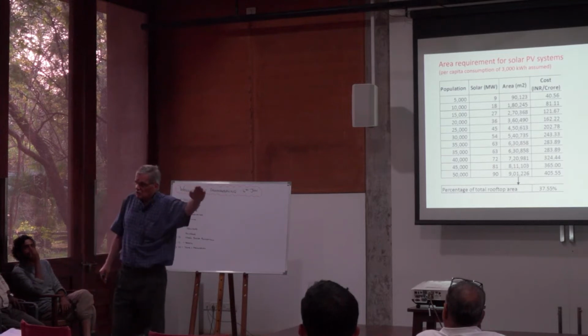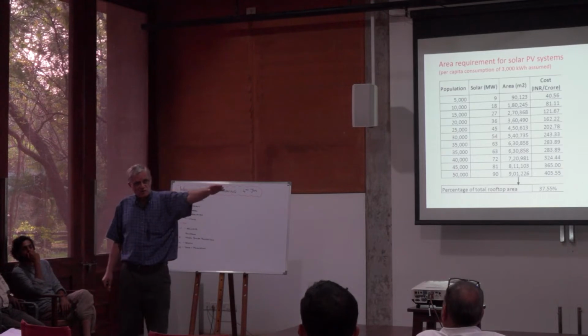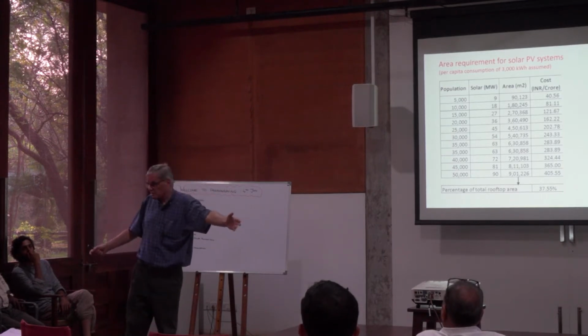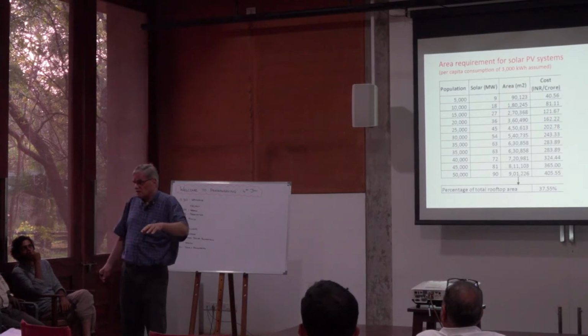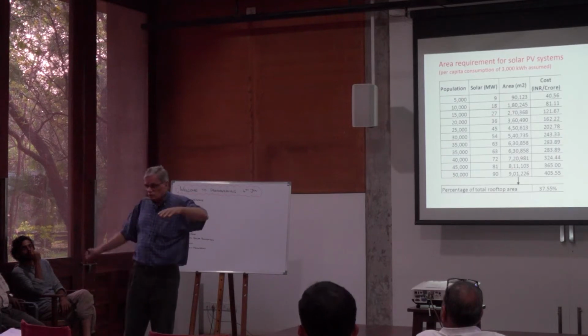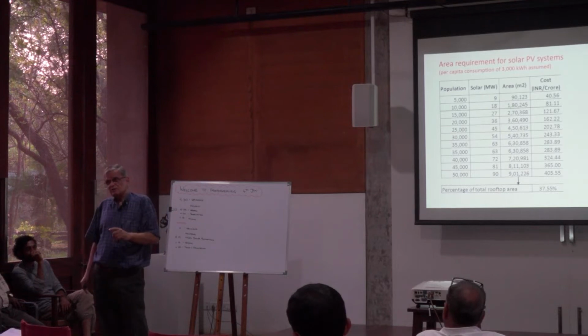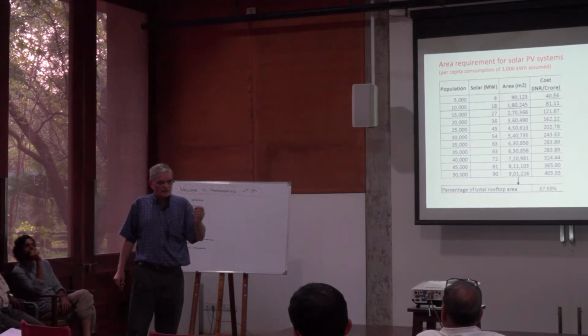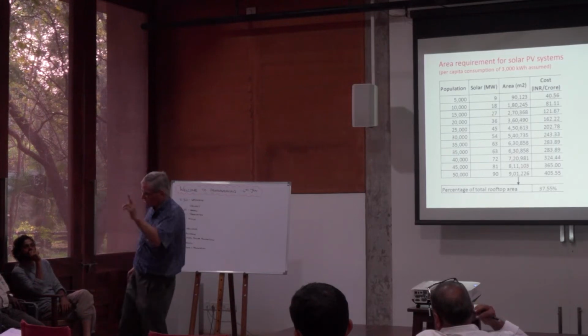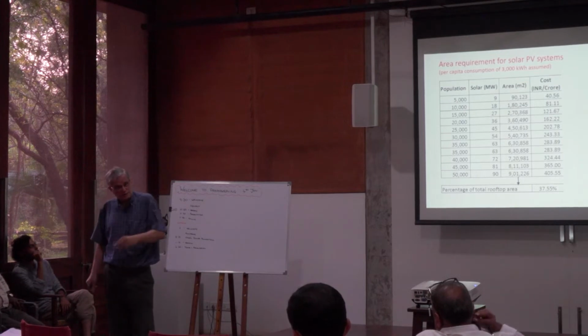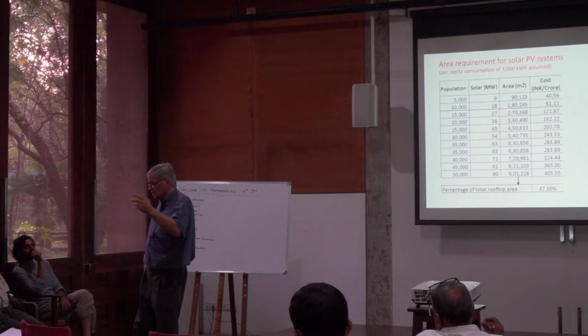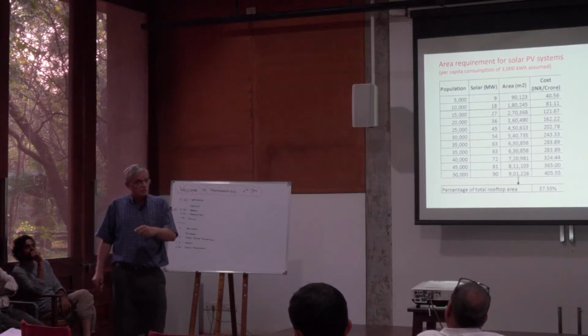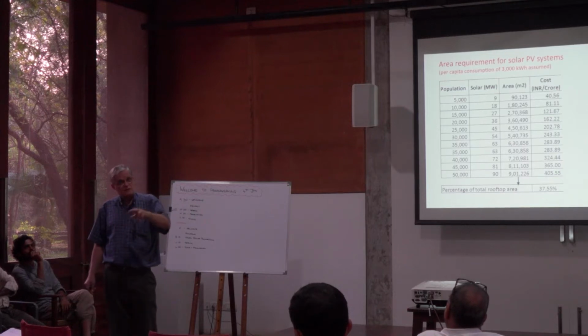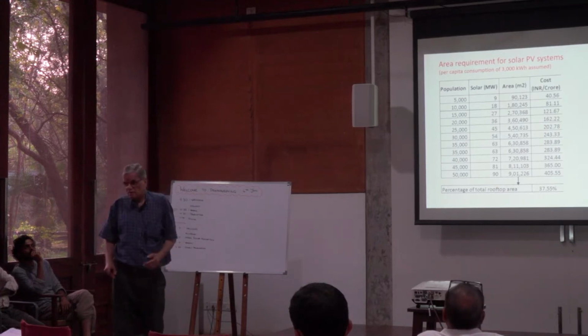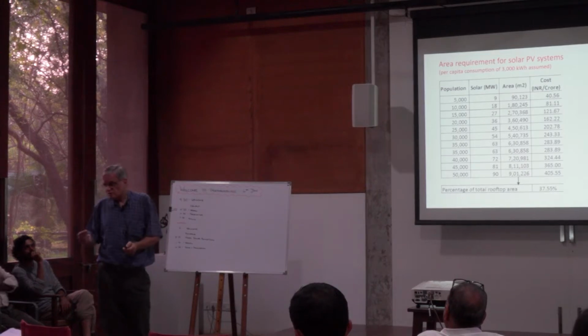Take for example the 650 megawatt plant of the Adani company in south Tamil Nadu — if a cloud formation passes over that system, 650 megawatts can suddenly drop to maybe 100 or 50 megawatts. Whereas if it's distributed, a cloud over Viluppuram doesn't mean there's a cloud over Chennai, so you spread your risk. Another big advantage of distributed solar: in centralized solar, if the substation near that 650 megawatt Adani plant has a problem, the whole 650 megawatts gets cut off from the grid, but demand continues. Whereas in rooftop solar, if a cable fails or a fuse blows in a particular street, generation stops but so does consumption. So distributed solar always matches generation with demand, whereas centralized solar doesn't. That's why we've been strong proponents of distributed rooftop solar.